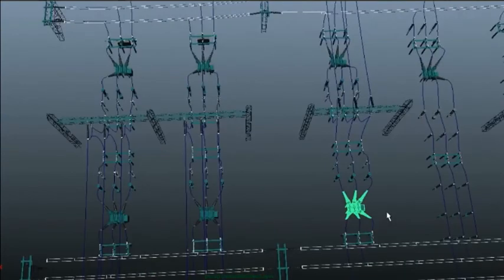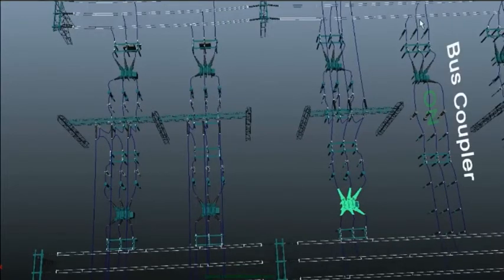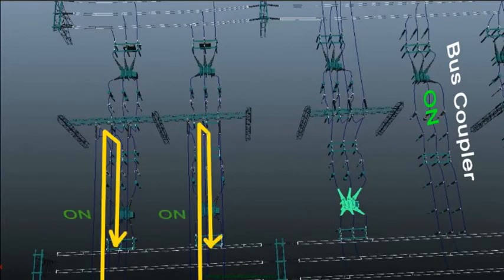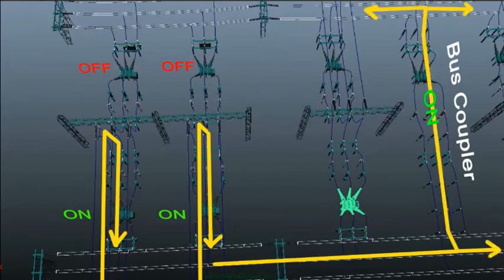Similarly, if we want to do the maintenance of this circuit breaker, then we have to ensure that the bus coupler is switched on. As power is coming from these lines and also reaching this bus, even if these breakers are at off position due to regular maintenance, both the buses are getting charged due to the bus coupler, and we could switch off this breaker and isolate it from the rest of the system by operating the isolators without interrupting the continuity of the power flow.